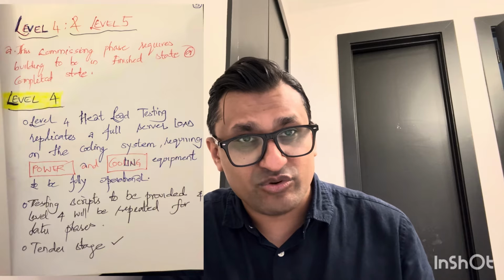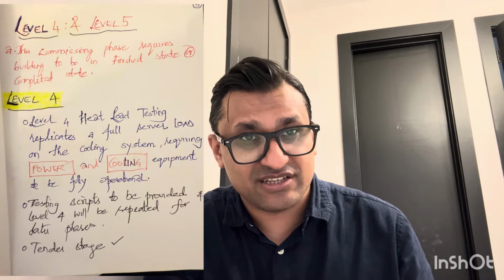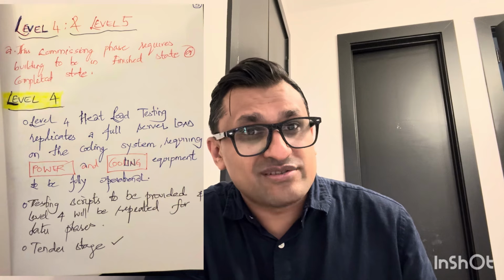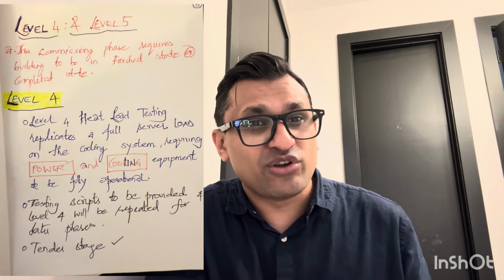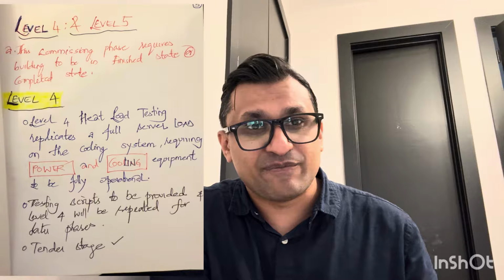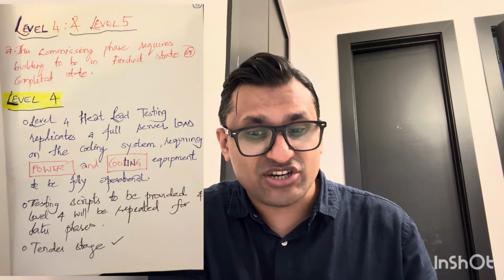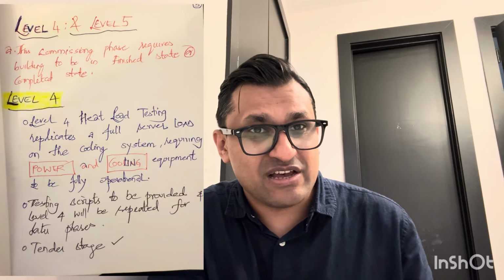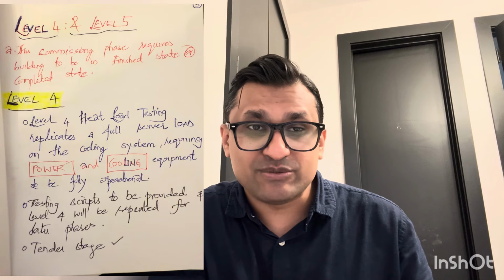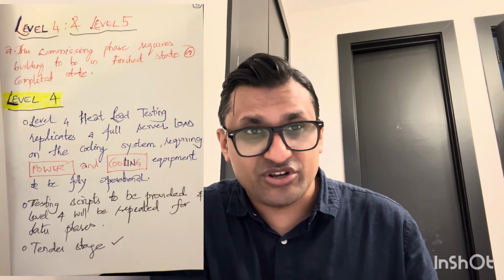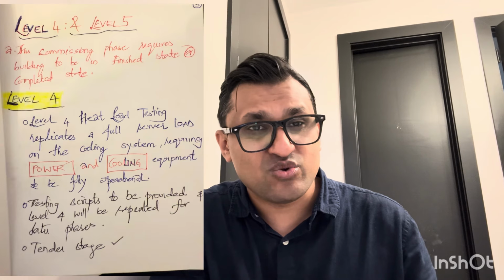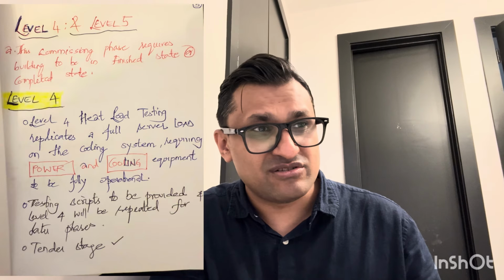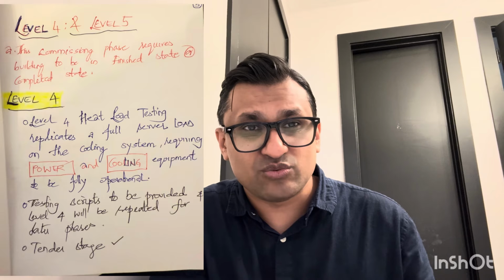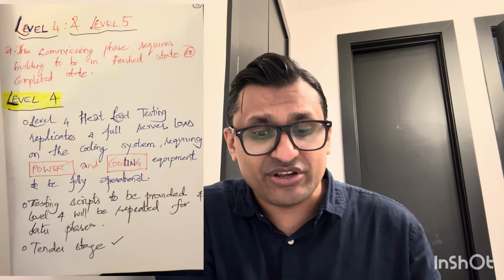Like you have the maximum number of servers that this data center can handle, for example 100,000 servers. You are testing it on a full load, making sure that the cooling system maintains that load. It doesn't crash out, it doesn't cause a failure in the system, and it requires power and cooling equipment to be fully operational. Obviously, you need power and you need the HVAC chillers, air handling units. You have the Liebert, Stulz units, whatever units you're using, they should be fully operational, and testing scripts to be provided. And level 4 will be repeated for later phases.